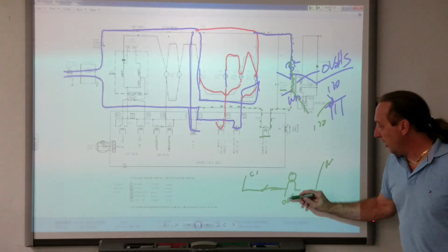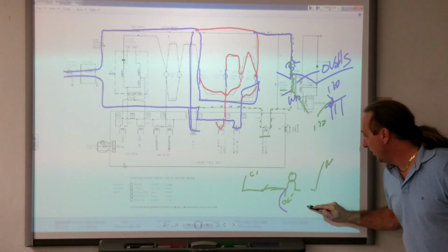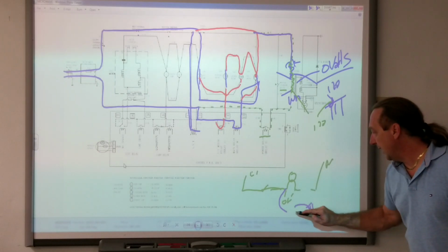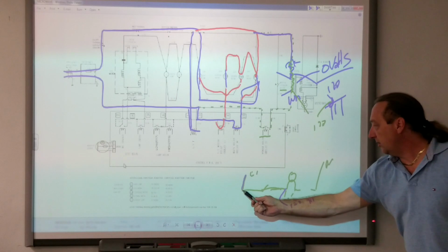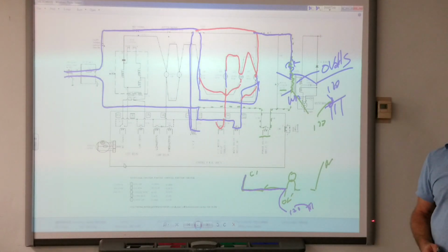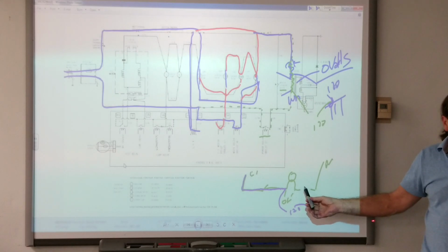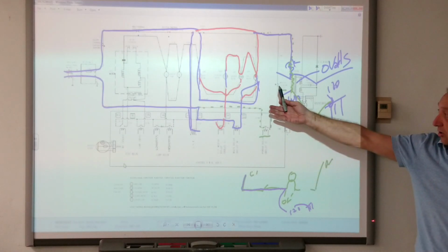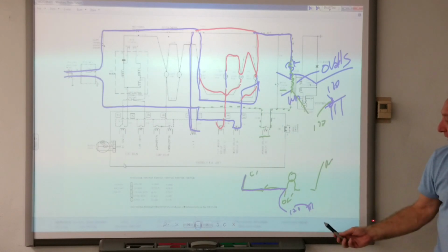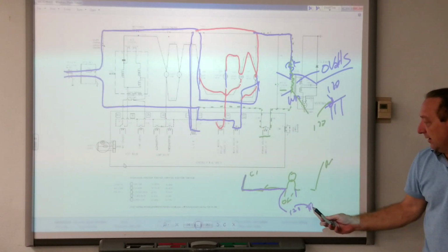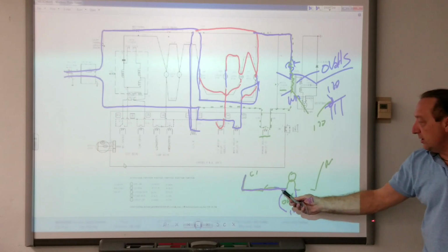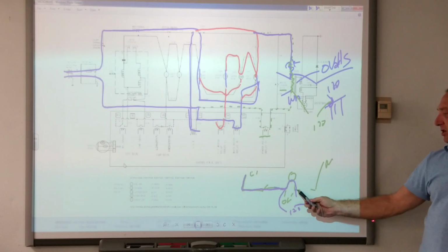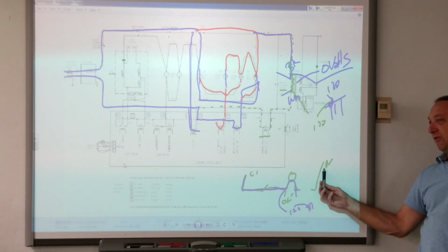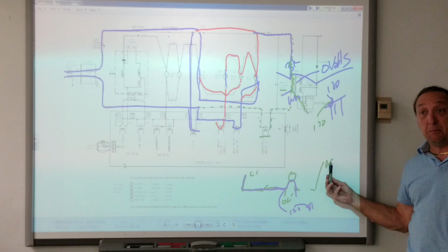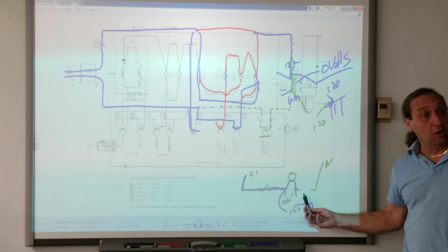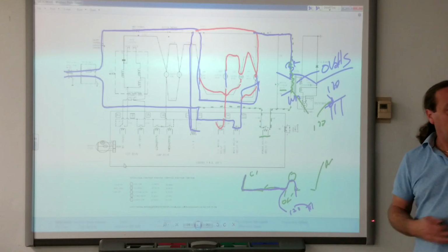Then I went from here to ground, using a different meter, and I had 120. That meant from here to here, I had line voltage. Now you can see I made the break here. In this circuit, you don't know where the break is. But if I move this one to here, and I get 120, line 1 is just coming through the light bulb. You're saying, but that's the neutral side. It's not neutral if I have something broken here. It's not getting back to neutral. If neutral was good, and I tested here to ground, I wouldn't get a reading.